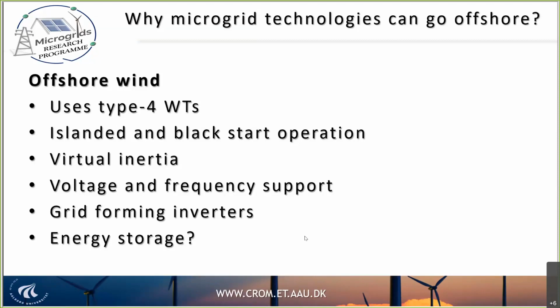Right now the big discussion is whether we should use grid following inverters like now, or shift to grid forming inverters. Recent studies suggest a percentage of your wind turbines could work as grid forming inverters. Another possibility is that your inverters normally work like grid following, and once you see an event where frequency goes out of normal ranges and predict something may happen, you could switch to grid forming control.